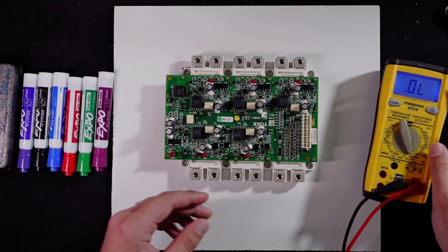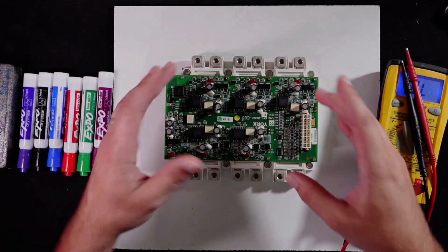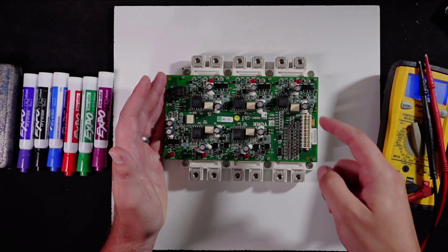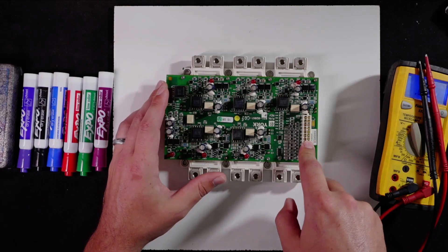And again, the question was, why do they fail? So the heat, the silicon breaks down. You can have any one of these little module components fail. These plugs that go into them, these are common failure points we struggle with. So you could have a bad plug issue.